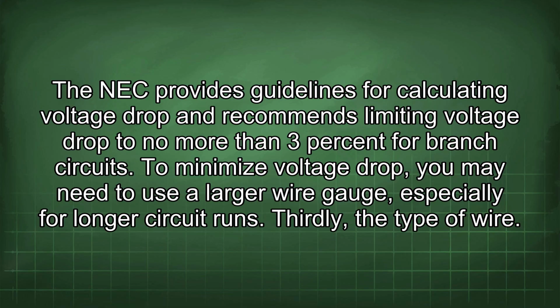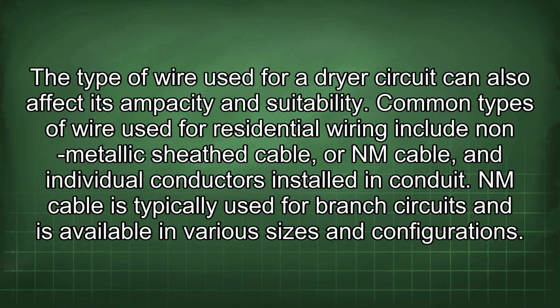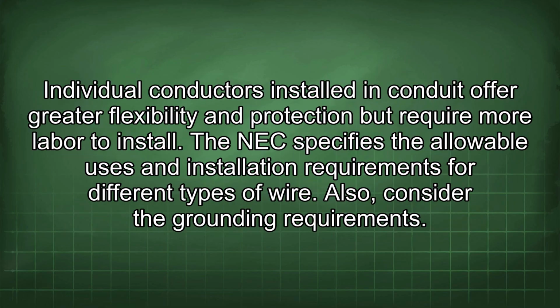Thirdly, the type of wire. The type of wire used for a dryer circuit can also affect its ampacity and suitability. Common types of wire used for residential wiring include non-metallic sheathed cable, or NM cable, and individual conductors installed in conduit. NM cable is typically used for branch circuits and is available in various sizes and configurations. Individual conductors installed in conduit offer greater flexibility and protection, but require more labor to install. The NEC specifies the allowable uses and installation requirements for different types of wire.